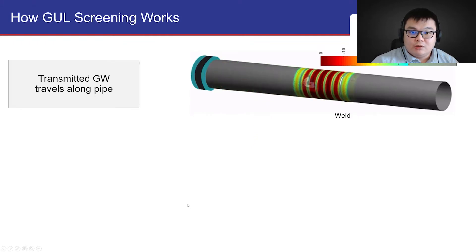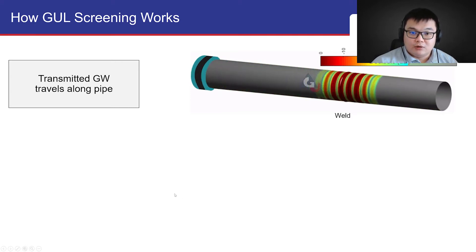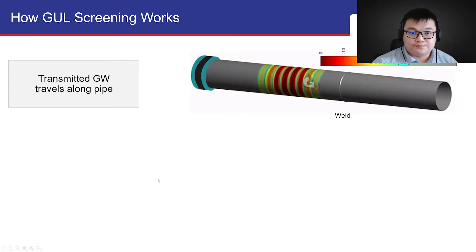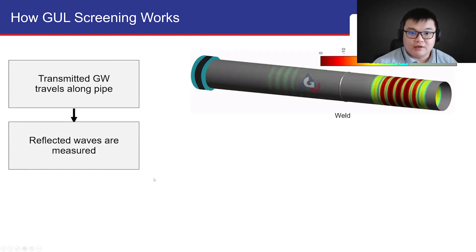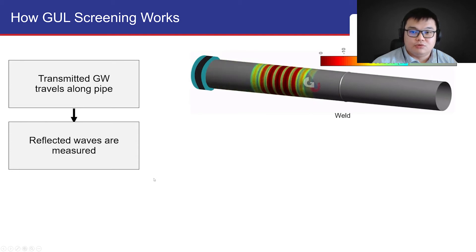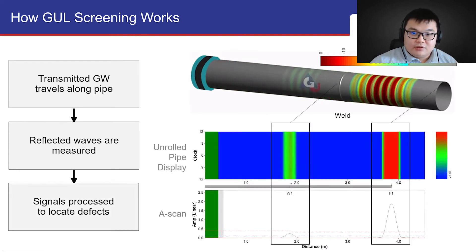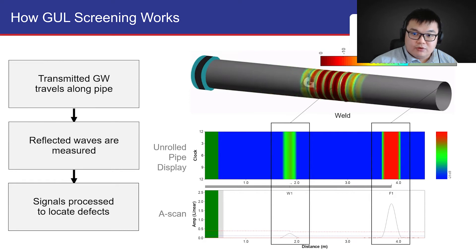GUL screening works by using a transducer ring to transmit GuidedWaves along the pipe axially. These GuidedWaves will then interact with existing pipe features or defects, and the reflected GuidedWaves are measured by the transducer ring. These GuidedWave signals are then processed by the WavePro software to produce two main results.